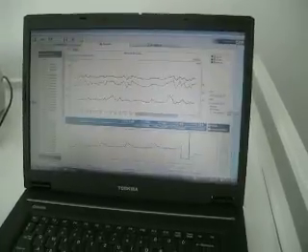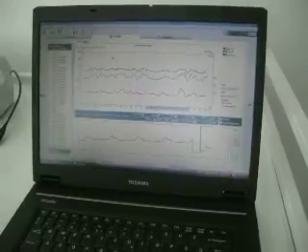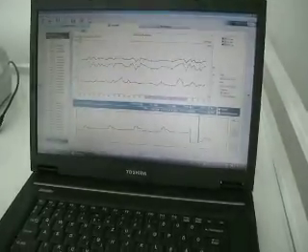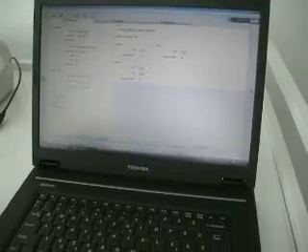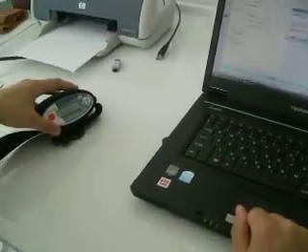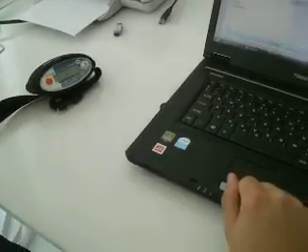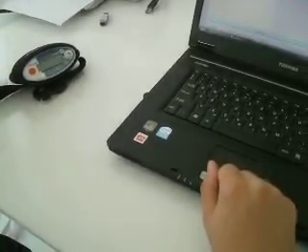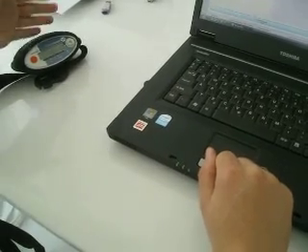Okay. There are several other options for the evaluation of the measurement. So if I select one measurement and go to the more detailed window, let's go first to the Study Data tab, and here you can change the day-night set. First, the device is programmed according to former knowledge of when the patient would go to bed and when the patient would wake up. After the measurement is completed, you should modify these settings according to the real data.